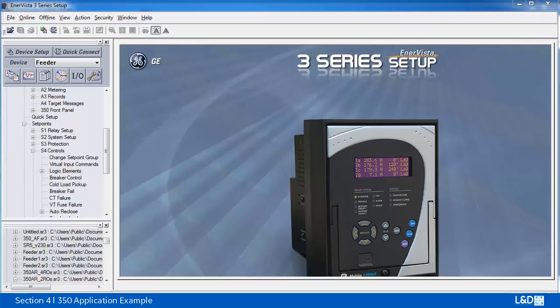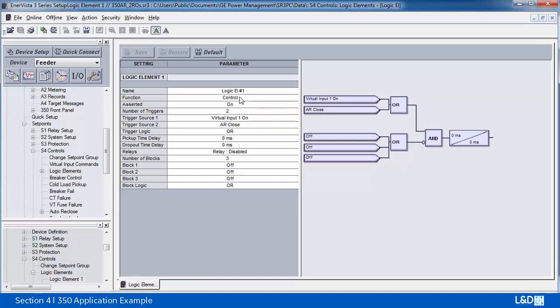Then the logic design is on the 850 side by using the logic designer tools. There's another way we can do it, by using the logic element of the 350 and pre-processing the signal into 2 logic elements and publishing to the 850. Then the 850 only needs 2 remote inputs. So we can use the power of the logic element of the 350. Under the logic element, we can enable logic element 1 to be control, asserted on. Then the trigger of 2 inputs: the first is virtual input 1 on, and the second trigger source is auto reclose.